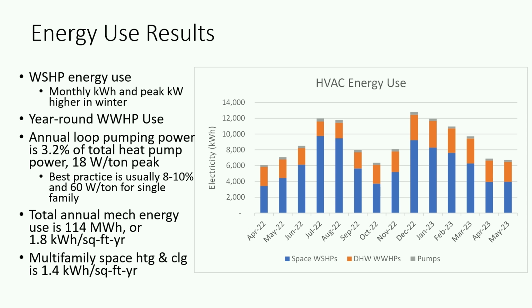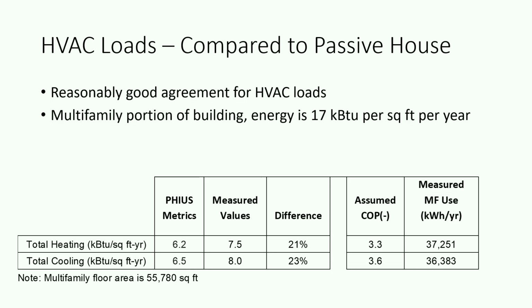Some of the overall facts: our total mechanical energy use per square foot was about 1.8 kilowatt-hours per year per square foot, and for just space heating and cooling, it was 1.4. So this was a passive house or a near passive house building, and there was a passive house analysis. And here is what the passive house tool predicted the heating loads were going to be, in 1,000 BTUs per square foot per year. The measured values are right here.